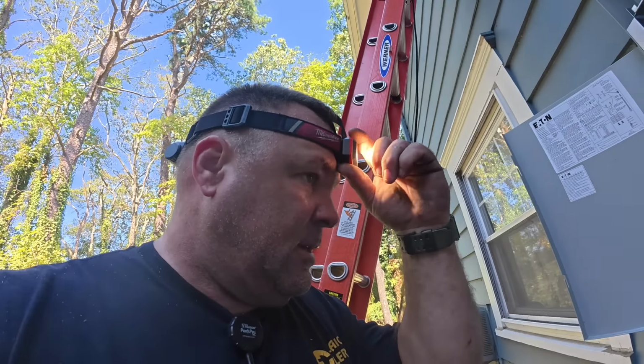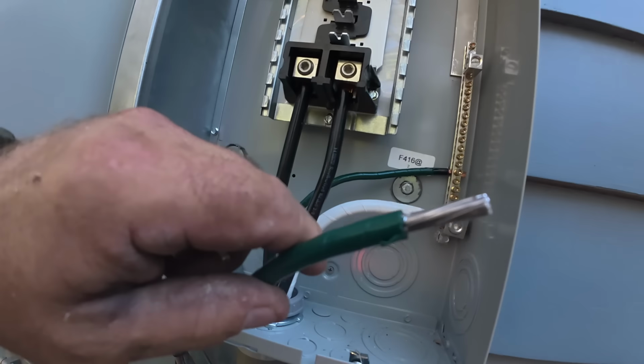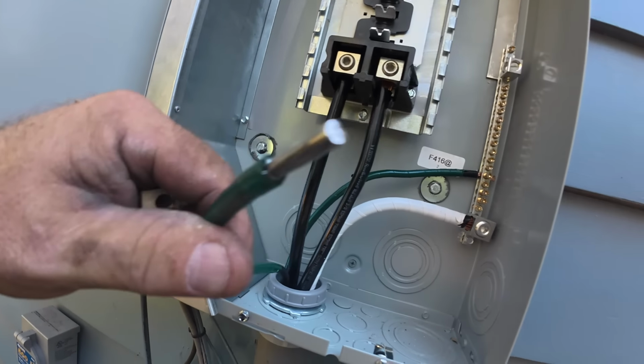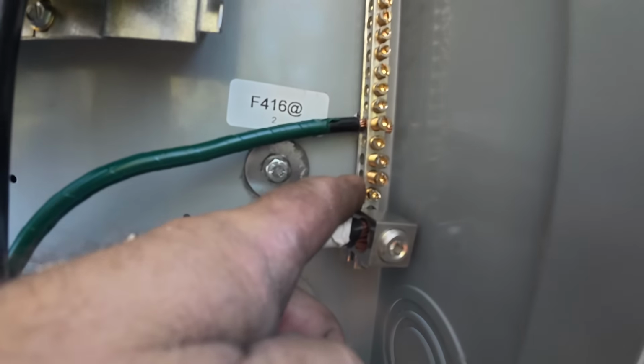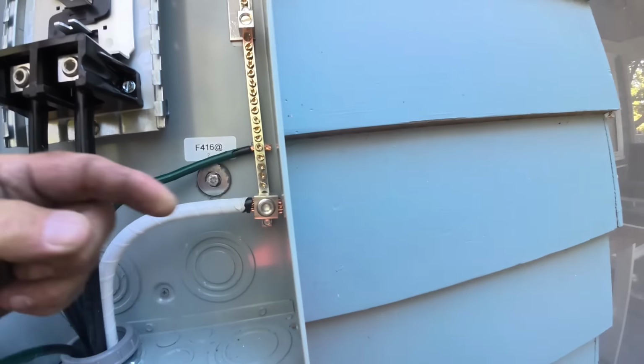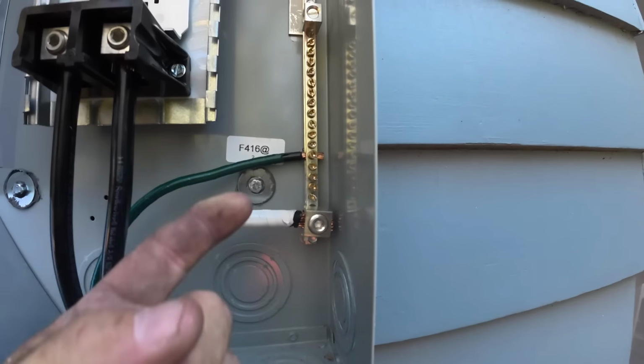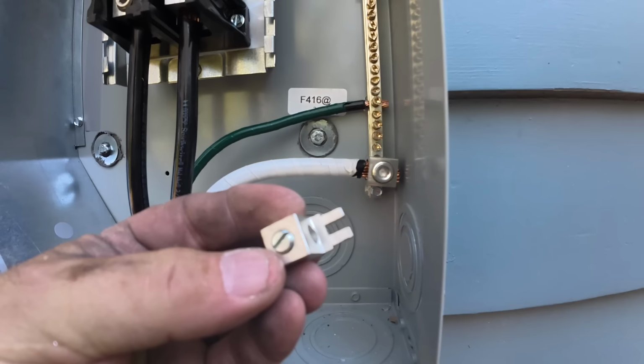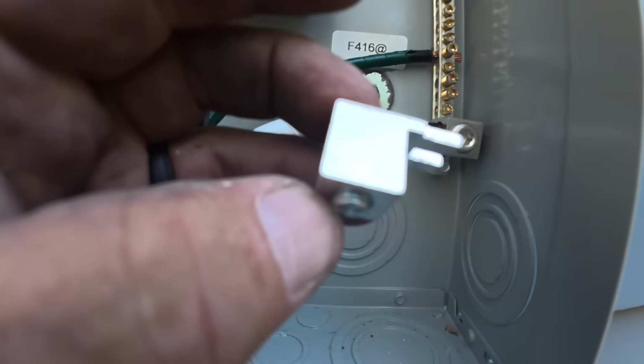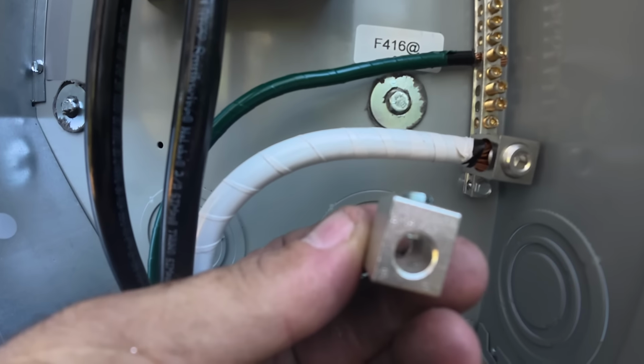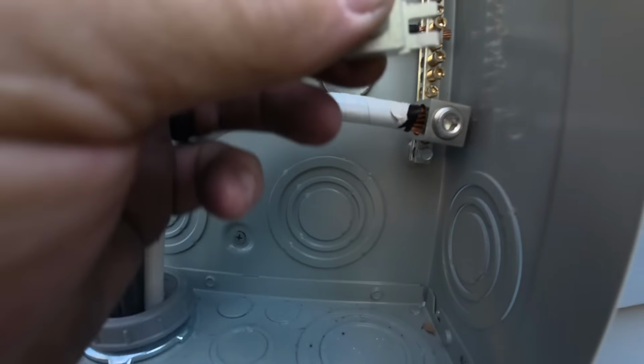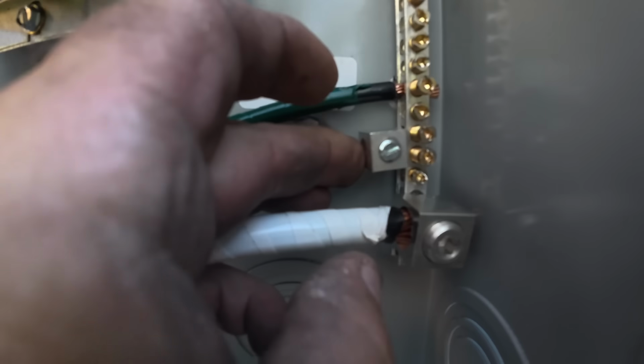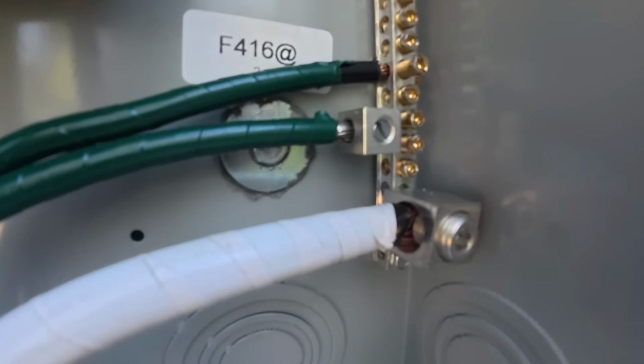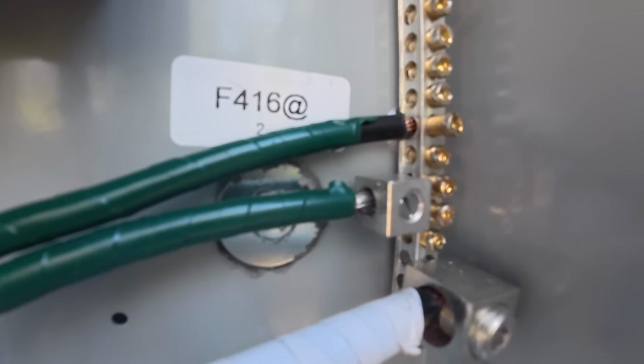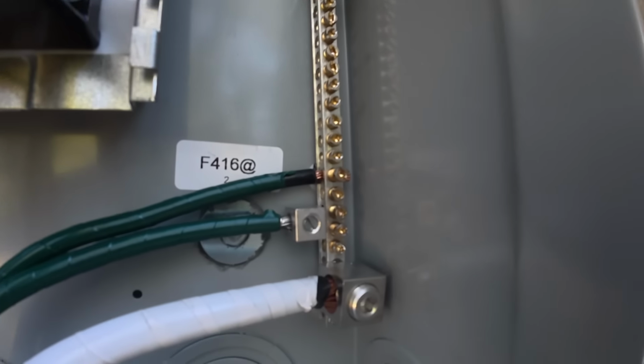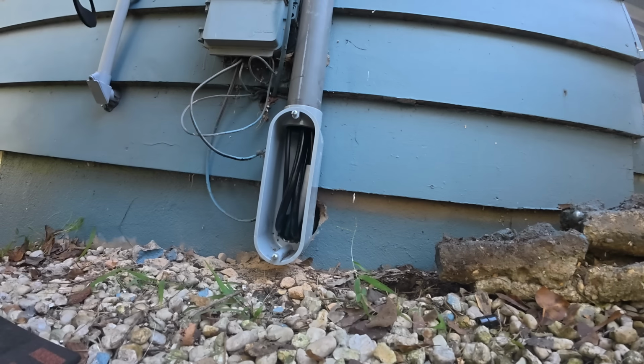Okay, here's what I use. This is a number 4 aluminum grounding electrode conductor, and I can't terminate on this bus because it's too big. Actually, the number 4 got on there, so the number 2 might fit. But what I'm going to show you is I use this thing right here, it's a fork, it's a lug. So I'm going to terminate inside that lug there, and then terminate the fork on the terminals, like just like that. So there it is after it's been terminated. Real simple. The only reason I didn't use the lug that's already built in is because I just barely made it, and you saw what happens when you don't do this.